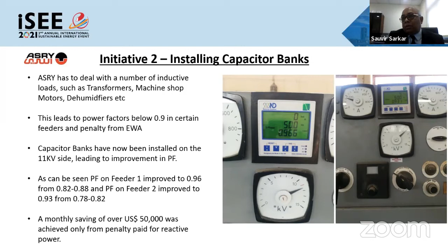That brought us to installing capacitor banks on the 11 kV side. On two feeders catering to the main motor-based loads, we saw an improvement in power factor from about 0.82-0.88 to 0.96. This is a big saving, monitored since November, approximately 50,000 US dollars a month, or 600,000 US dollars a year, compared to spending about 400,000 US dollars on these capacitor banks. This is a huge saving for us.